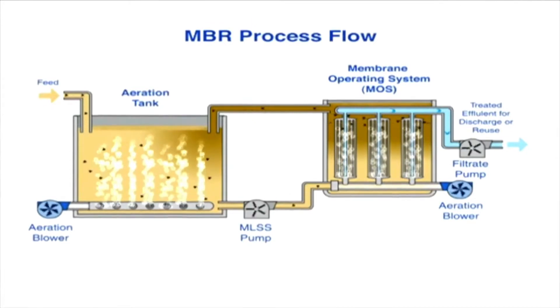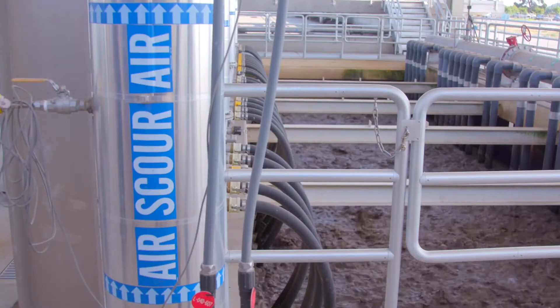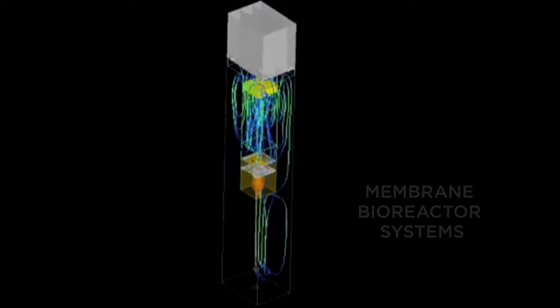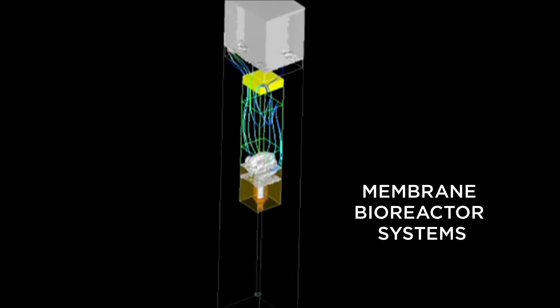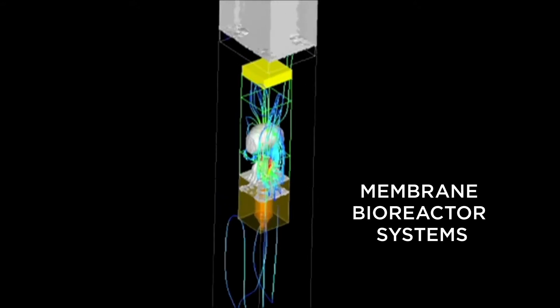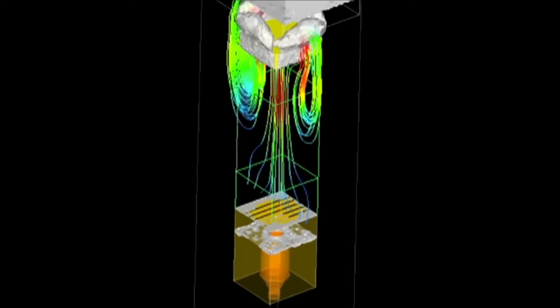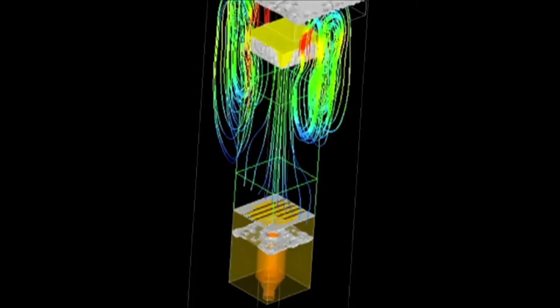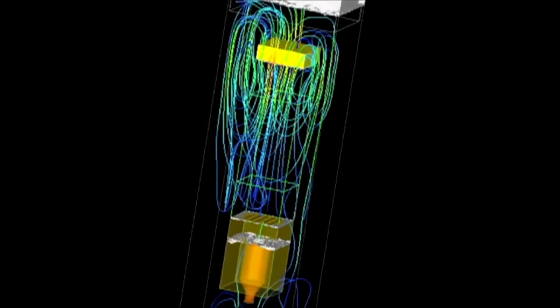Just like other activated sludge systems, air aeration plays a vital role in Membrane Bioreactor or MBR systems. This computer simulation shows the burst of energy created in a Memcor MBR module. As the large bubbles of air produced by the MemPulse device rise through the module, the two-phase flow created by MemPulse maximizes shear on the membrane surface by creating both upflow and downflow zones around the rising slug of air.